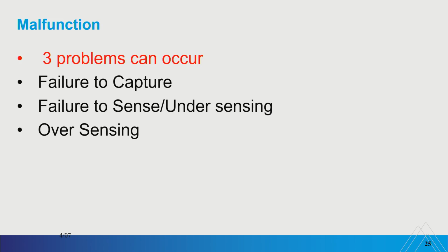The other thing that could happen, it could be called is pacing inappropriately. That also means failure to sense or undersensing. So always try to convert it back to one of these three things. It makes it easier to fix.